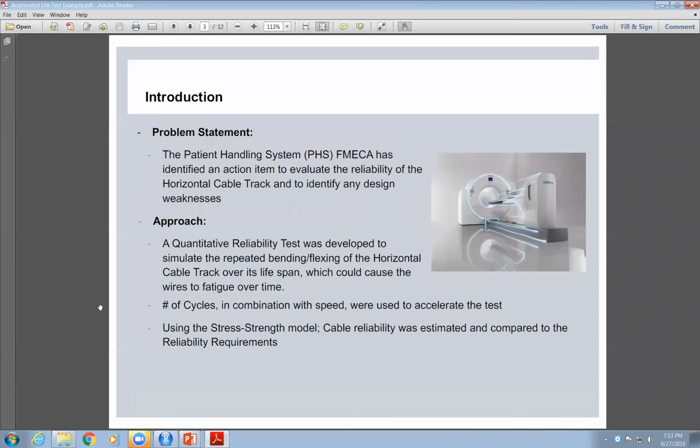It talks a little bit about the types of failure modes and if a specific wire fails, what could happen. So we had two extra wires. If it fails, it's not a big deal. A couple of them will stop the system, and one of them is used for service. To just give you a little bit of idea and background about the severity of the failure. Definitely, if one of those fails, this is a big deal. If this one, who cares, right? So you need to start thinking about that.